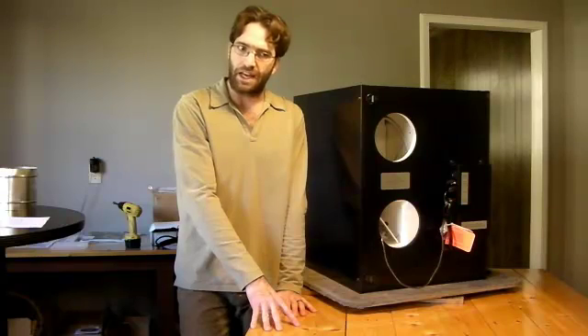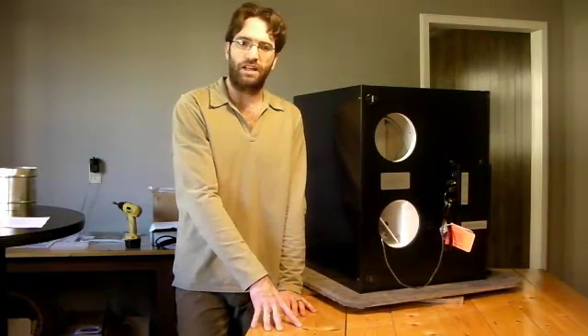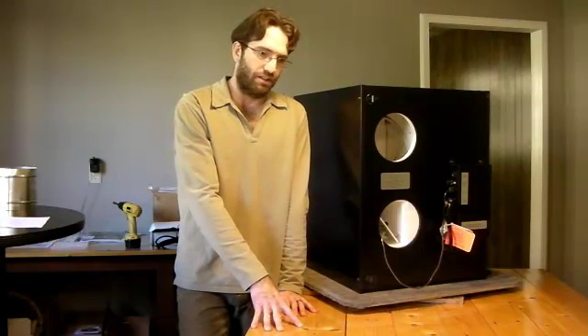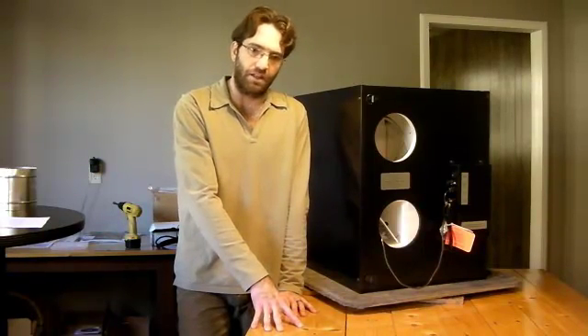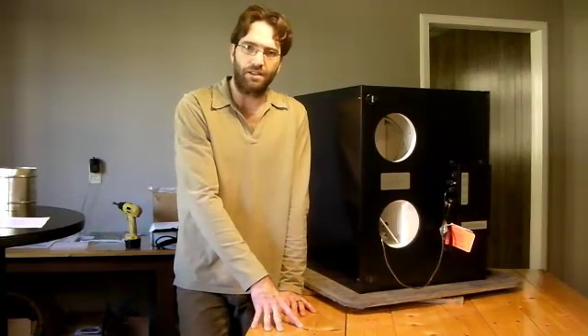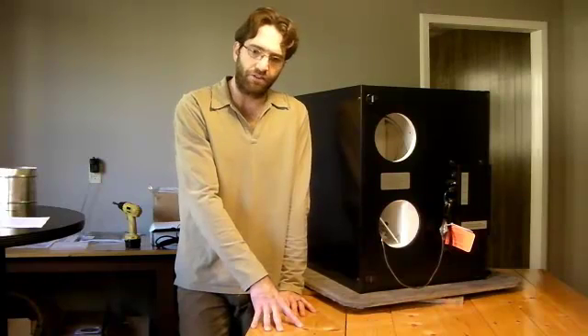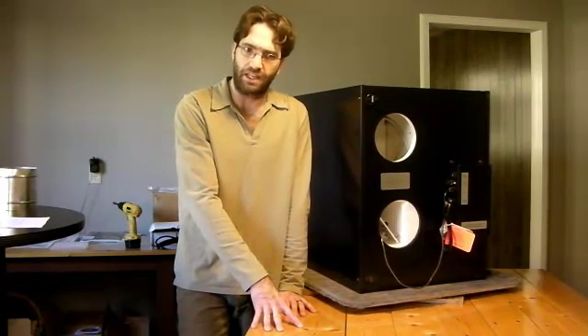An ERV, in that case, is going to capture some of that humidity and keep it inside. Still, in both of those cases, when the outside humidity is less than the inside, both an ERV and an HRV are going to dehumidify the house. The HRV is going to dehumidify it much faster than the ERV.